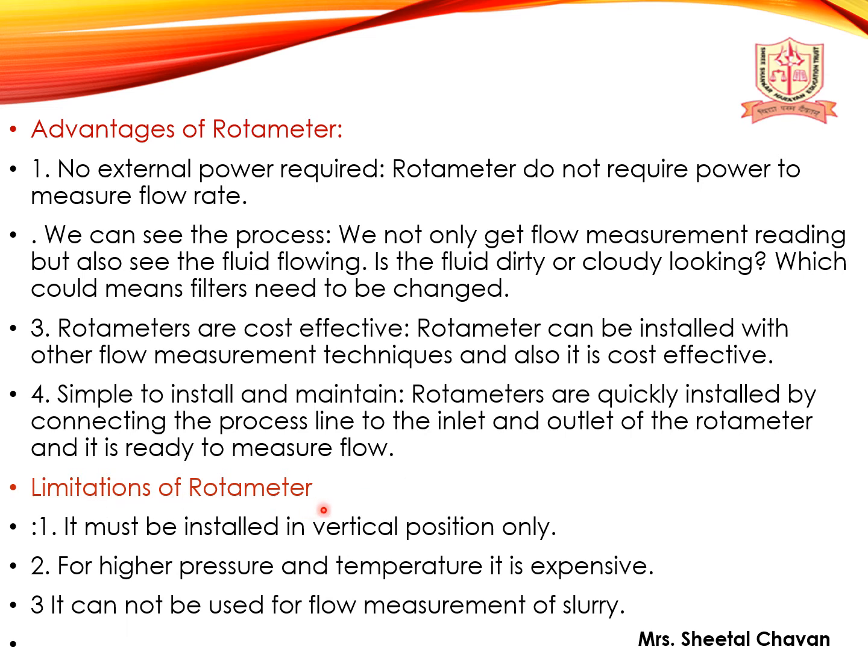Then, what are the limitations of rotameter? It must be installed in a vertical position only. For higher pressure and temperature, it is expensive. It cannot be used for flow measurement of slurry.